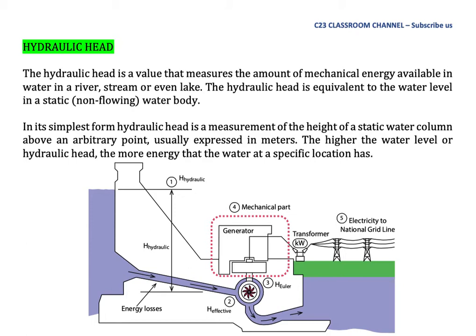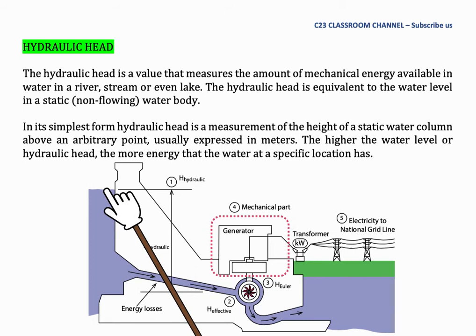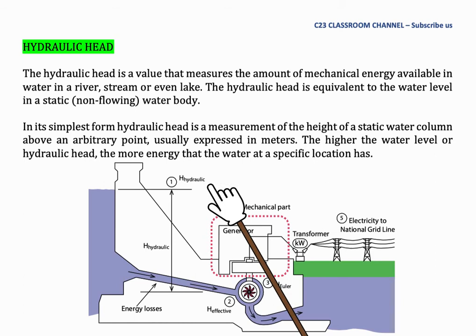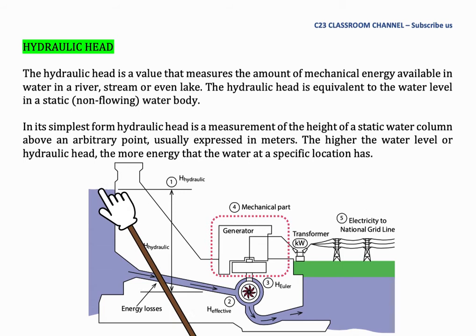The higher the water level or hydraulic head, the more energy that the water at a specific location has. If we see this diagram, we have a dam here and this is the water level, and this water will flow to the Francis turbine here with a pipe system. The hydraulic head is the distance from the level of water here to the central point of the Francis turbine.